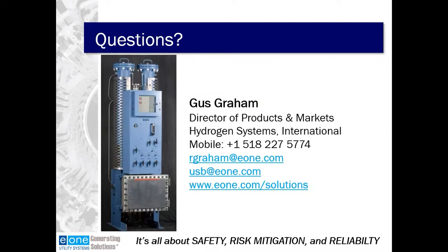Okay, thank you. The next question: what parameter will alert you first, hydrogen purity or hydrogen dew point, in case of any abnormality in the generator? It depends on the failure mode. The hydrogen purity reading is going to look for the ingress of air into your generator, which predominantly will come through the seal oil system. The purity meter typically will not detect the presence of dew point. So your purity meter is looking for a different situation.